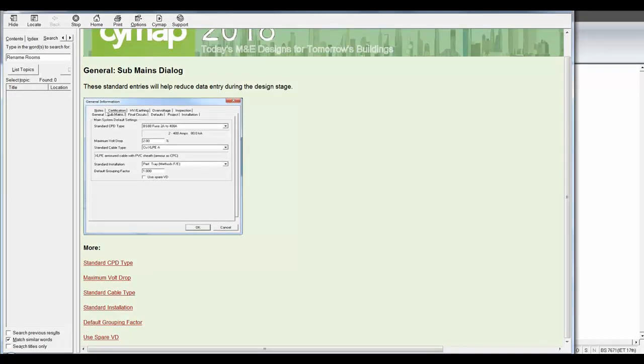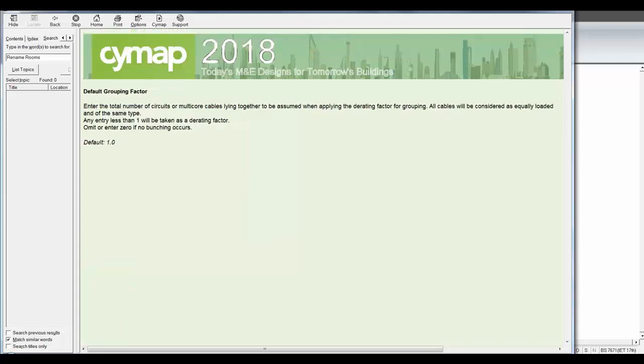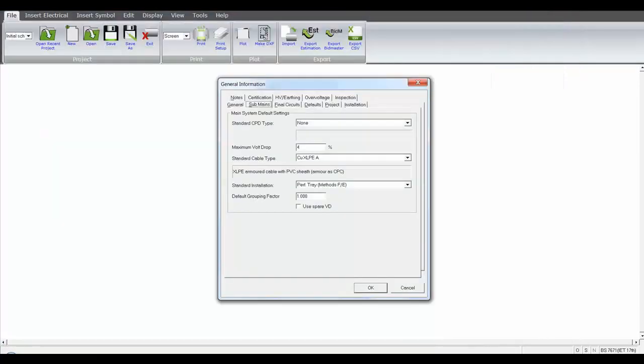So here we are in the General Information tab, and then you can interrogate the subject matter. It's always best to close down the manual when you finish with it because it is context sensitive. If you don't close it down, it will only reveal the previous subject you were looking at, which may be totally irrelevant to your current subject matter. The next phase for us is to select the preferred breaker type we want to see on our submains. This is the maximum voltage drop percentage that's been applied based on the previous entry, in this case 4%.